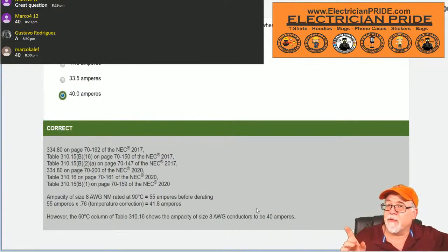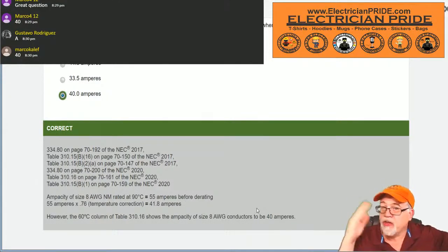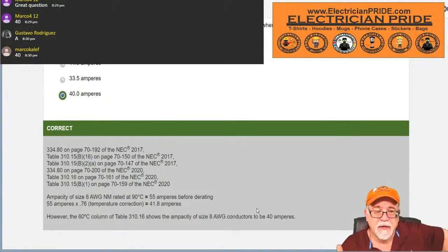Remember what it said in 334.80? You could use a 90 for adjustment and correction as long as the value didn't exceed that of the 60-degree column. So that conductor could have been worth 50 amps after adjustment and correction. It doesn't mean you can put 50 amps on it. You still can't violate the terminal limitation or the rules in the code that say what the insulation value is and what column you can use.